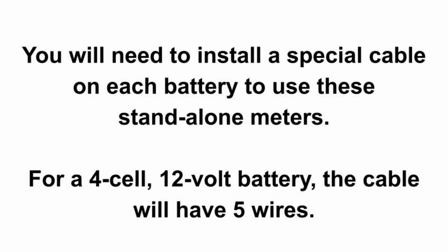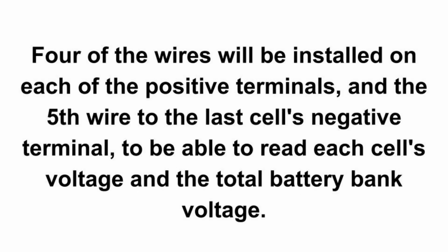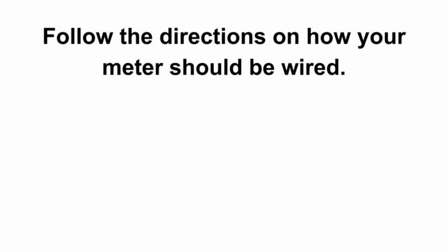For a 4-cell, 12-volt battery, the cable will have 5 wires. 4 of the wires will be installed on each of the positive terminals and the 5th wire to the last cell's negative terminal to be able to read each cell's voltage and the total battery bank voltage. Follow the directions on how your meter should be wired.